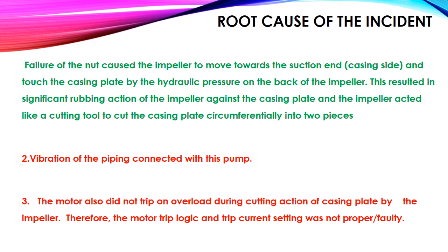Failure of the lock nut caused the impeller to move towards the suction end and touch the casing plate by hydraulic pressure on the back of the impeller. This resulted in significant rubbing action of the impeller against the casing plate, and the impeller acted like a cutting tool to cut the casing plate circumferentially into two pieces. Vibration of the piping connected with this pump. The motor also did not trip on overload during the cutting action of the casing plate by the impeller. Therefore, the motor trip logic and trip current setting was not working properly, or may be faulty.